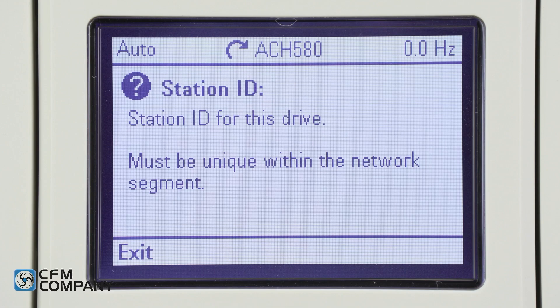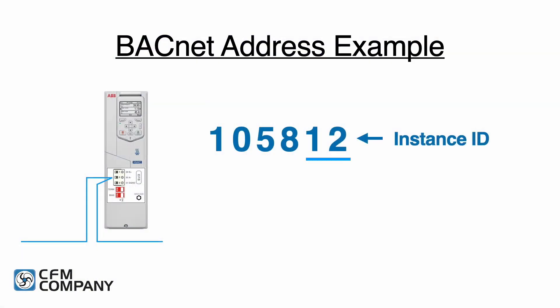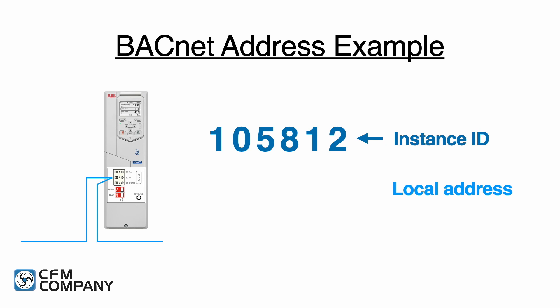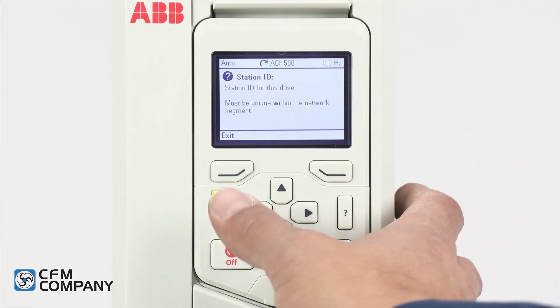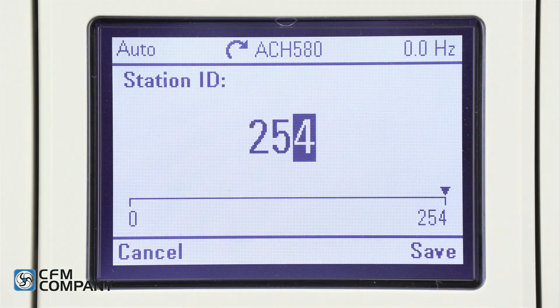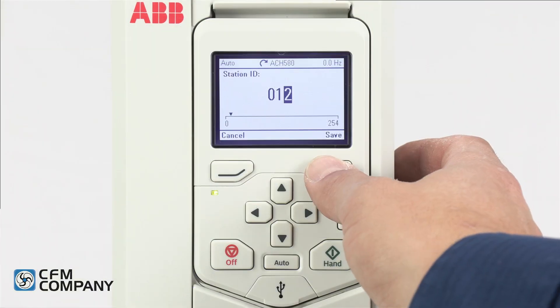The station ID for this drive must be unique within the network segment. The information for this example shows that the last two digits of the instance ID will be the local address. The local address can also be referred to as the MAC address, the station ID, or the device address. The local ID is not always the last two digits of the instance ID — it can also be a unique number between 1 and 247. Press exit to return to the communication setup menu. Press edit at station ID, change the value to 12, and press save.